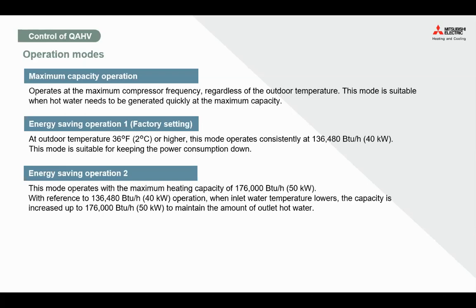Or you can do it on the energy saving mode. So basically what's happening is at 2 degrees C or higher, the unit will be acting constantly at 136 MBH. So as outside temperature gets a little bit warmer and warmer, you may not need as much hot water as before. And lastly, the energy saving mode will be able to operate up to 176 MBH of capacity.